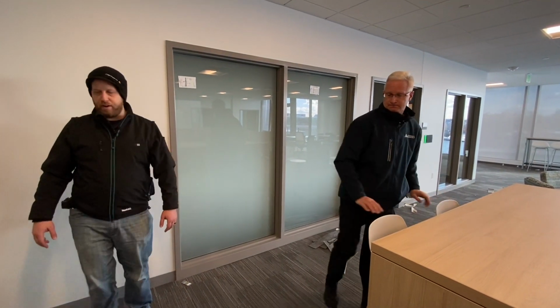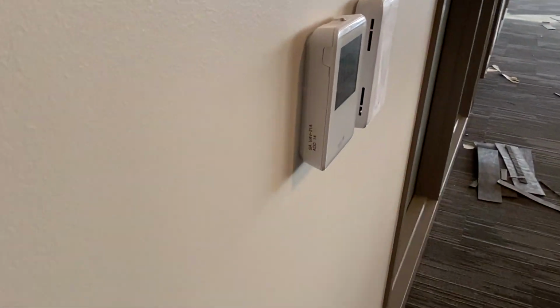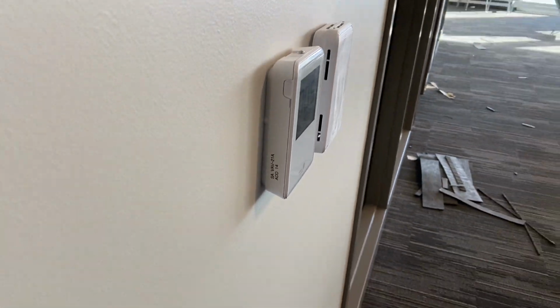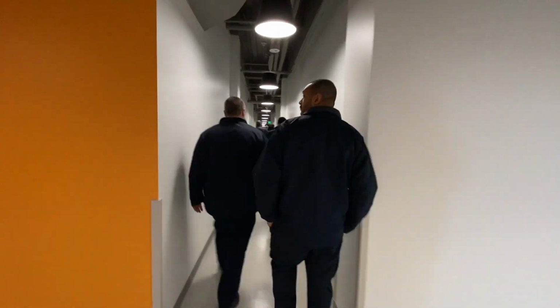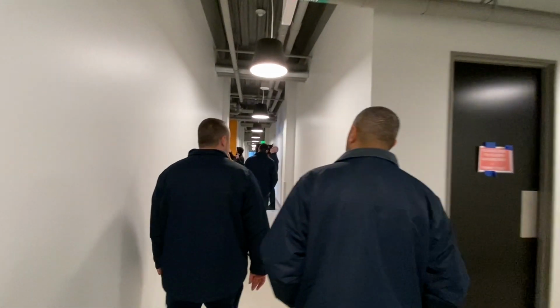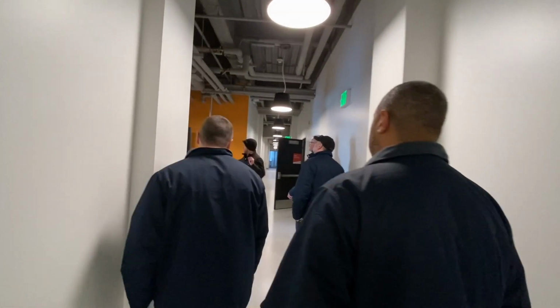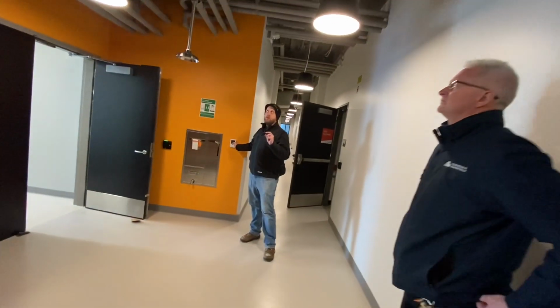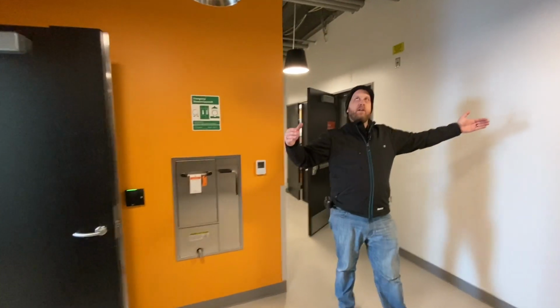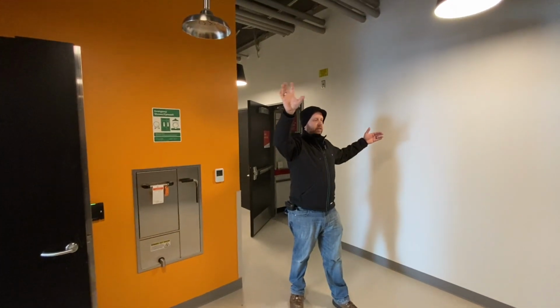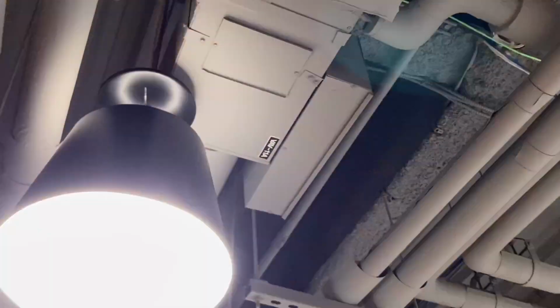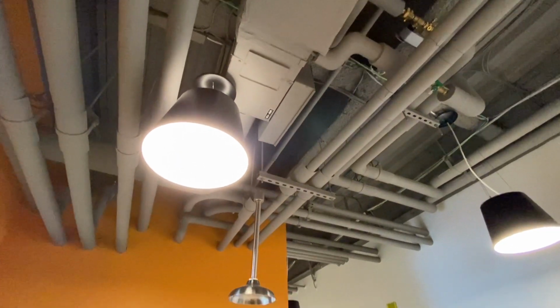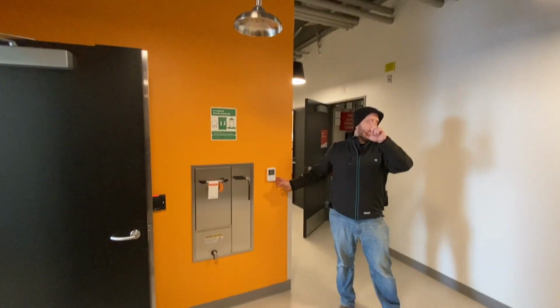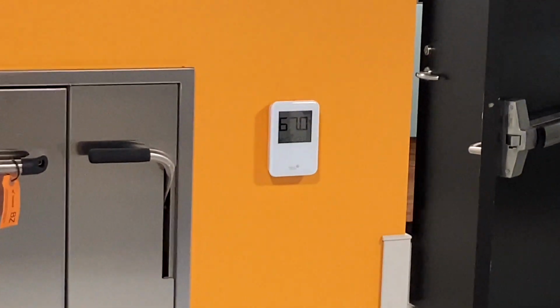I'm going to show you where that VRF system and some of our controllers are here on the 6th floor. But in the hallways, we have a couple of VAV boxes that we control. It's a little weird. There are two boxes, I think, outside these doors, and I think it's mirrored on the other side. We have our controllers, but these are actually fed from DOAS 1. So it's lab air, but since it's not doing a laboratory sequence, it's just providing air into these hallways. We do have our controllers in these boxes for the hallways because it's not considered a lab space, so it's our controllers, but DOAS 1 air.